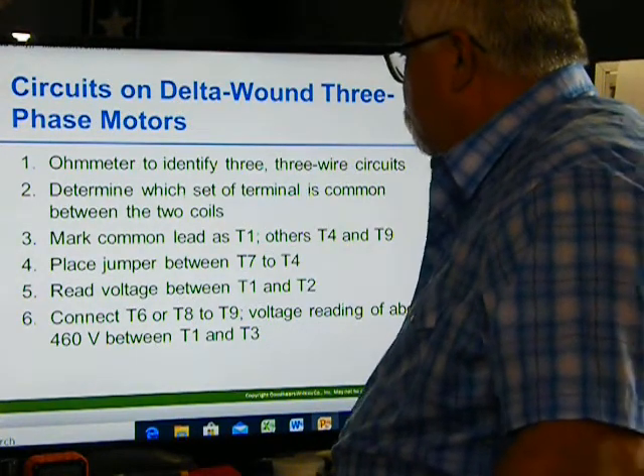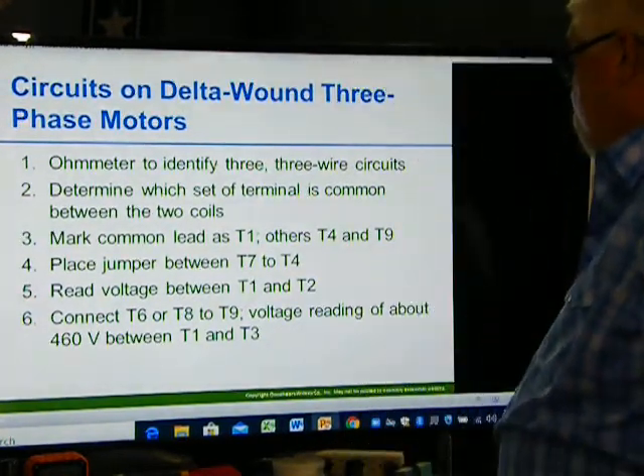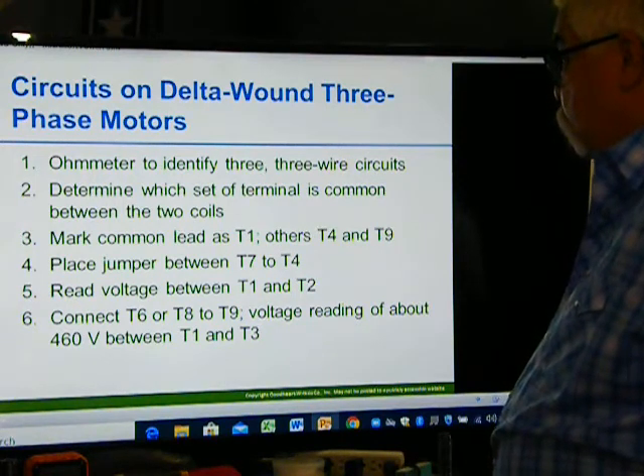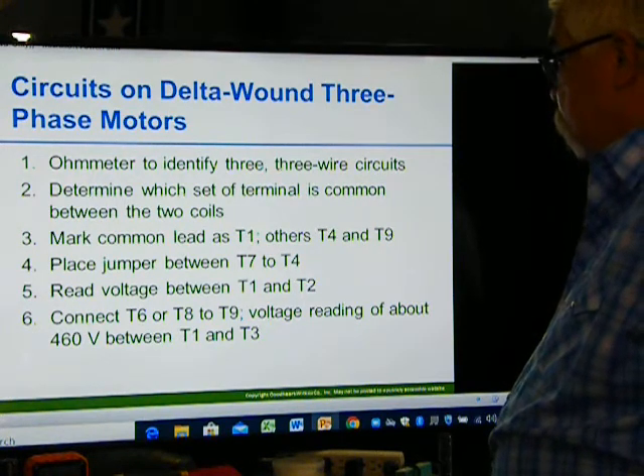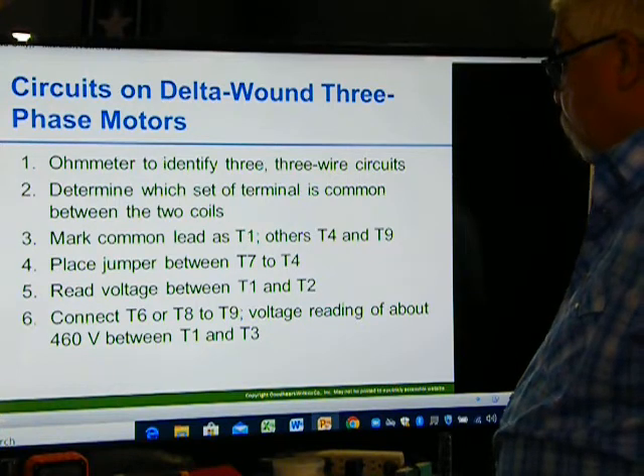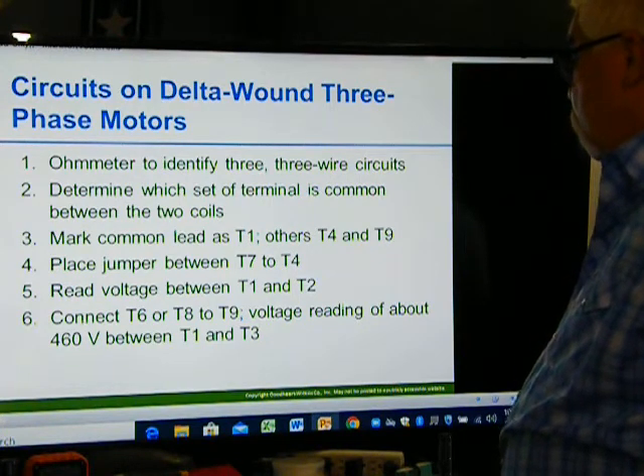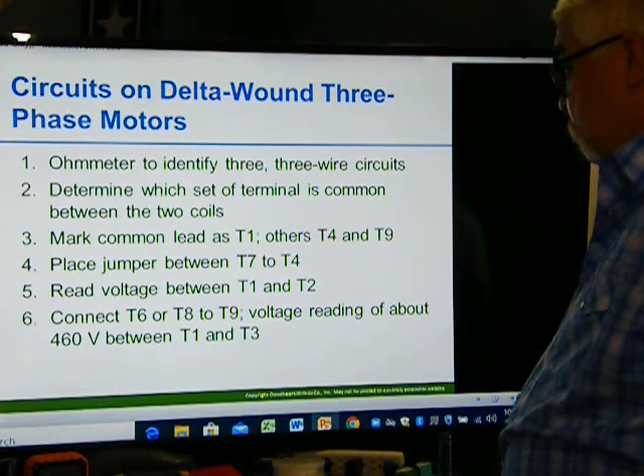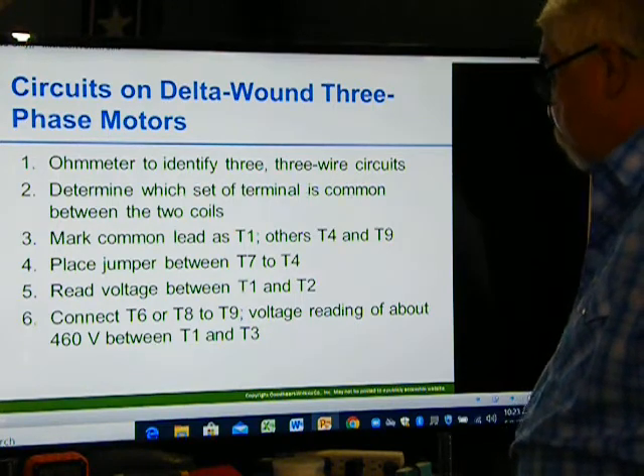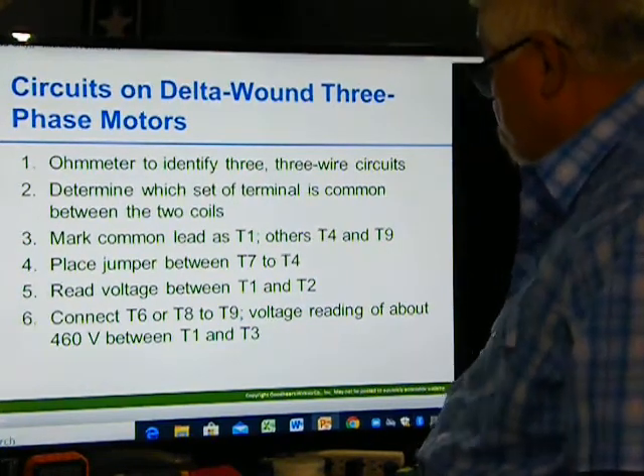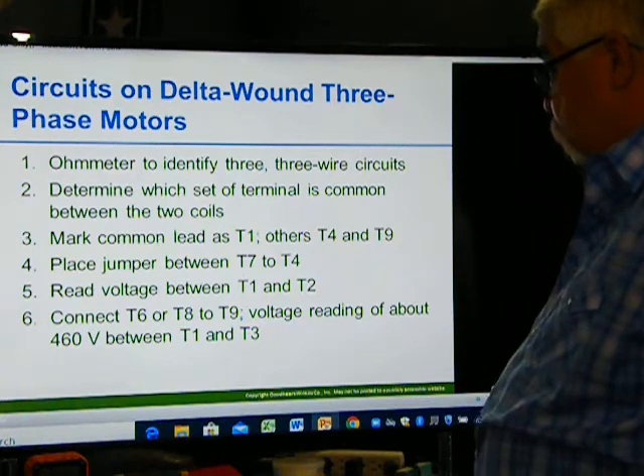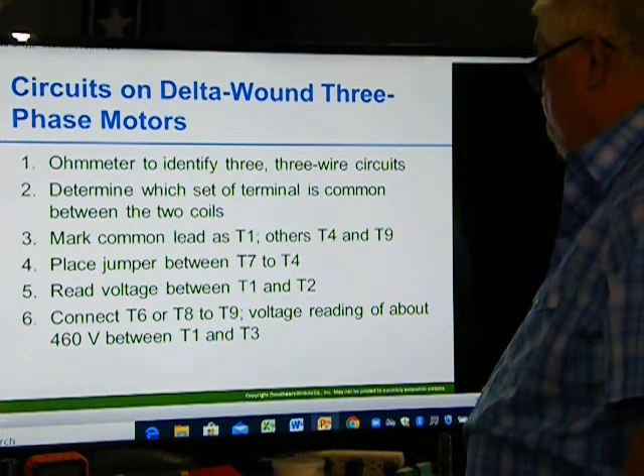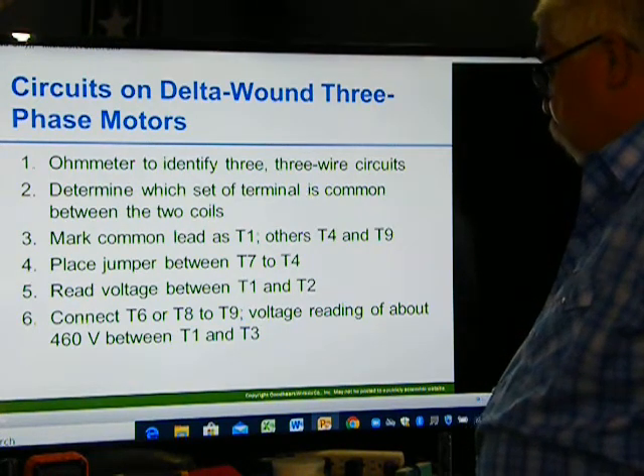For delta wound, it says use the ohmmeter to identify the 3-wire circuit. Determine which set of terminals is common between the two. Mark the common leads T1, and the others T4 and T9. Place a jumper between T7 and T4. Read the voltage between T1 and T2. Connect T6 or T8 to T9. The voltage reading should be about 460 volts between T1 and T3.